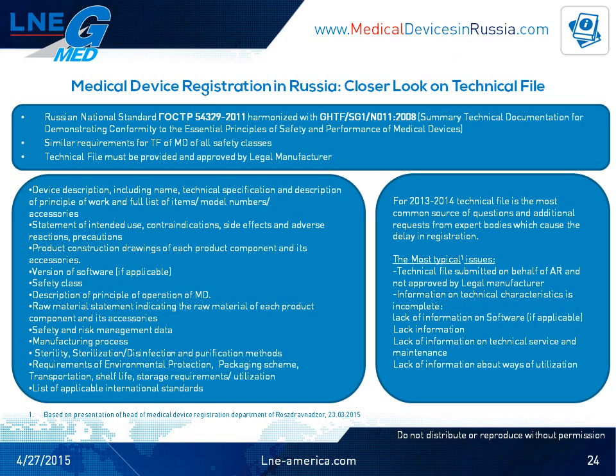Then you should provide a statement of intended use and statement of indication for use with information of contraindications, side effects, adverse reactions, and precautions. Of course, safety class should be mentioned in the technical file. Then raw material statement with description of materials for each product component and for medical device and accessories. Safety and risk management data in form of risk assessment and risk control should be provided.